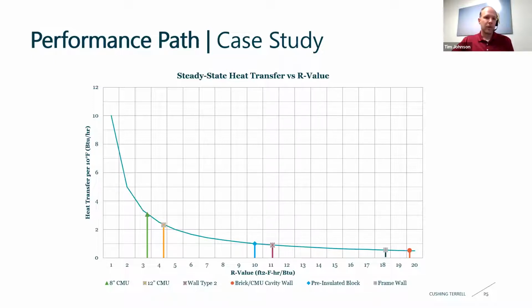If we start from essentially an R value of 1, going all the way down to about an R value of 20, there's definitely diminishing returns in terms of heat transfer through that wall. And right here at about 11 is where code currently requires us to be in Idaho. But about 10 is kind of your typical integral insulated CMU block. So if we go just below code, there's really not a lot of difference in heat transfer. So that's one place we've been seeing the performance-based code compliance modeling coming in handy.